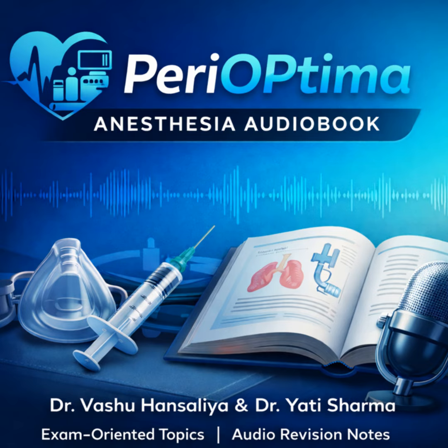Any other common faults? Misplaced FGI or APL valve. Yeah. If the FGI is introduced between the patient and the inspiratory valve, fresh gas can be forced back down the expiratory limb, disrupting the one-way flow. Or if the APL valve is placed incorrectly, it can lead to rebreathing.